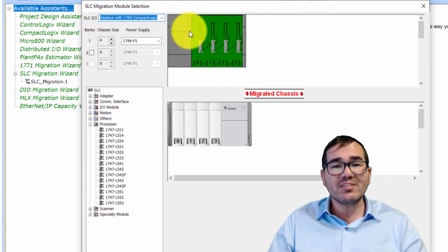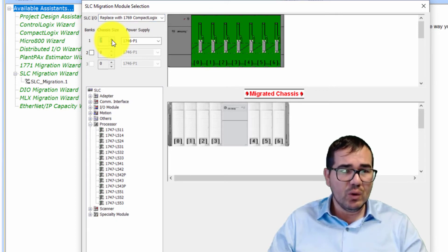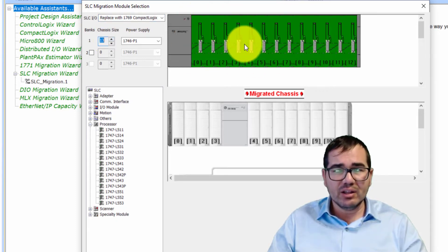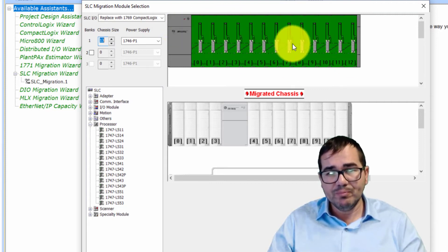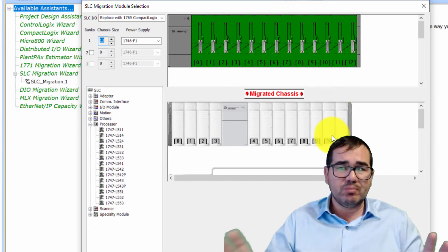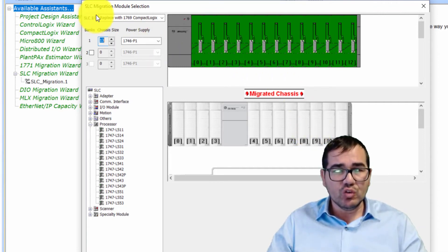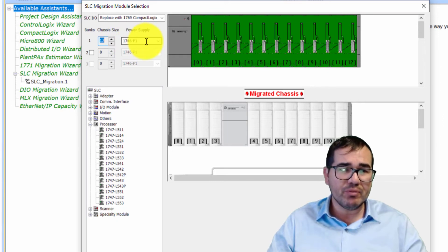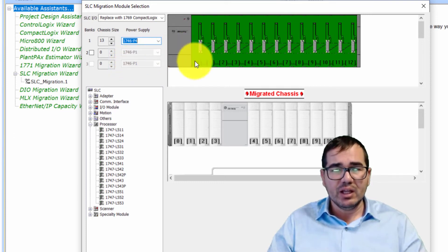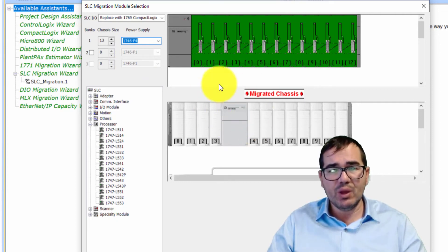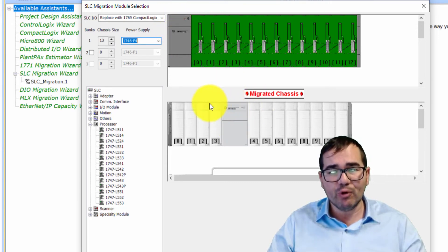Now you need to choose the size of your chassis. My chassis is 13 slots, so I'm going to select 13 slots. As you can see, you choose your real existing SLC 500 chassis size and it automatically shows the compatible CompactLogix equivalent. For the power supply, I'm selecting the 1746-P4, and it automatically selects the matching CompactLogix power supply.